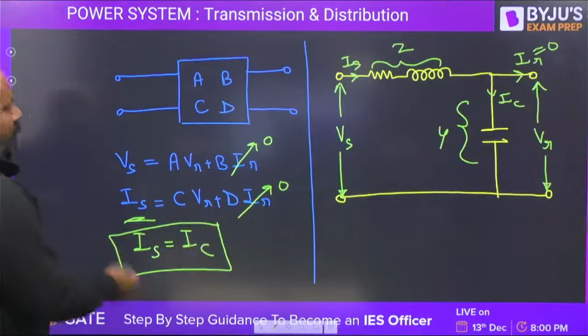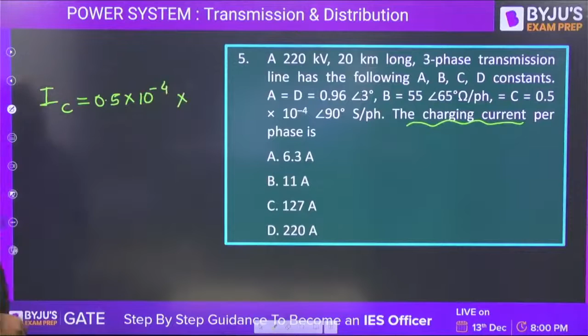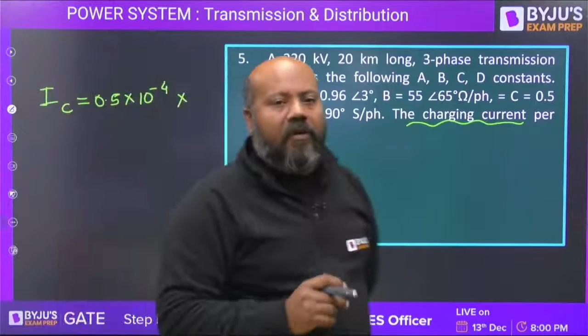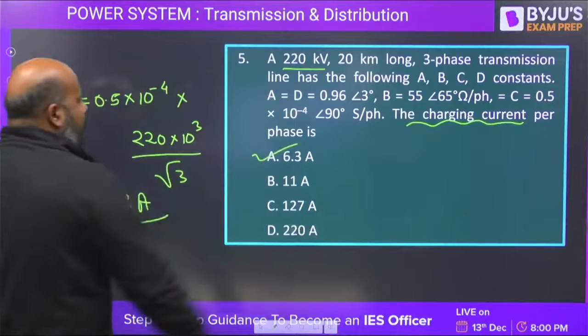So, what is going to be your charging current? What is C? We are only concerned with the magnitude. So, it is 0.5 into 10 to the power minus 4. Now, per phase voltage you have to write, because always remember, when you are dealing with ABCD parameters, you always deal in terms of per phase analysis. And charging current you will always find per phase. So, voltage is 220 kilovolt. Change it to the per phase value, divided by root 3. Somewhere around 6.3 amperes you will be getting as your charging current.